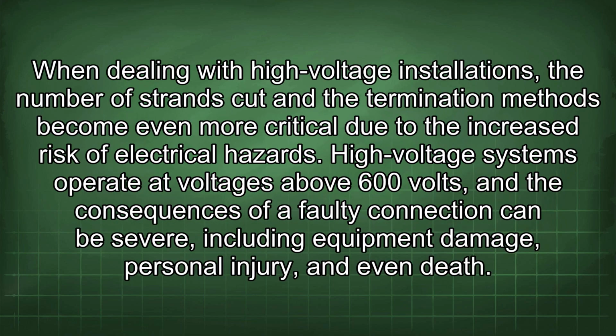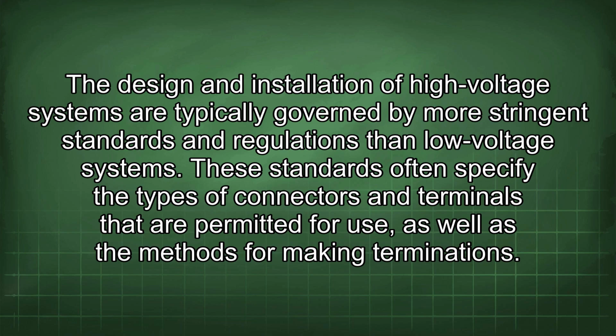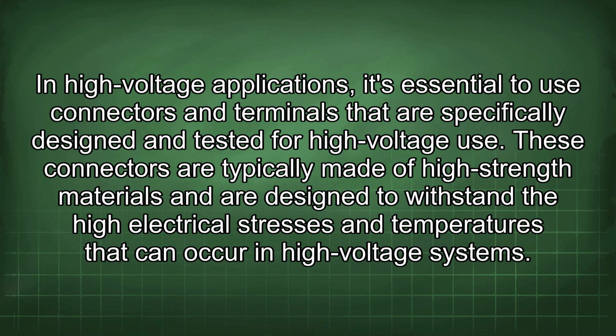When dealing with high voltage installations, the number of strands cut and the termination methods become even more critical due to the increased risk of electrical hazards. High voltage systems operate at voltages above 600 volts, and the consequences of a faulty connection can be severe, including equipment damage, personal injury, and even death. The design and installation of high voltage systems are typically governed by more stringent standards and regulations than low voltage systems. These standards often specify the types of connectors and terminals that are permitted for use, as well as the methods for making terminations. In high voltage applications, it's essential to use connectors and terminals that are specifically designed and tested for high voltage use.